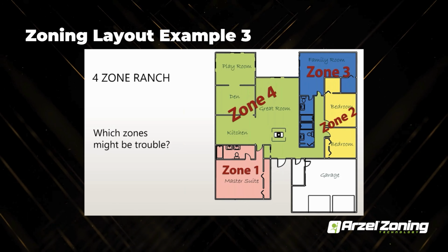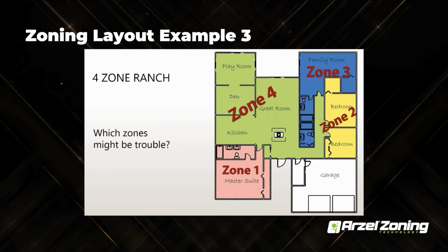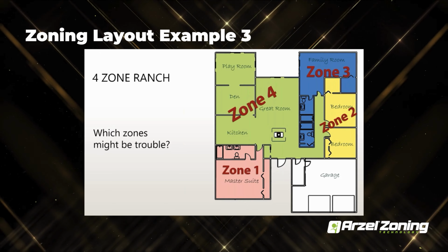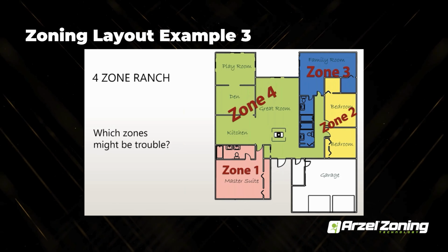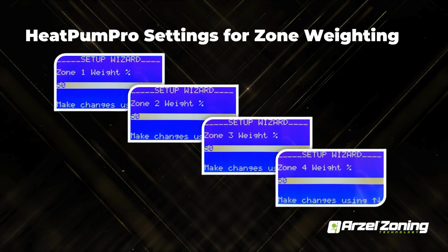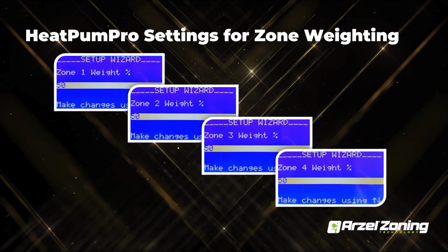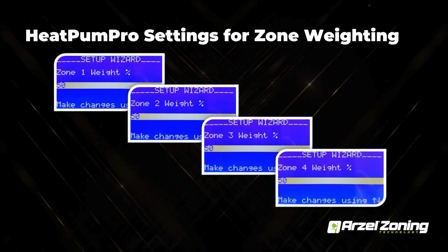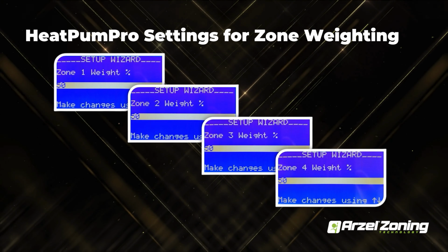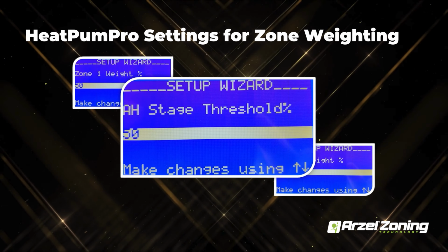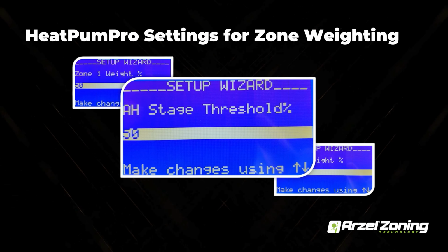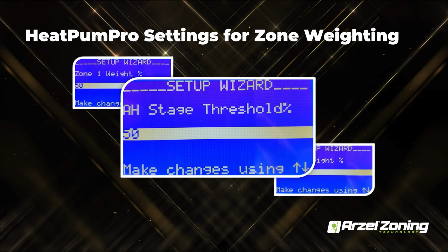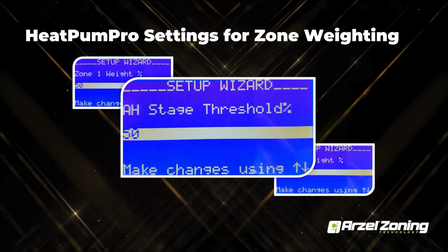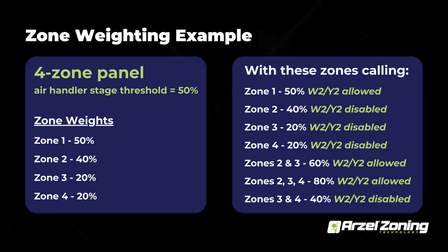If you do that, you can definitely zone a home very similar to this and still achieve the outcome that you're looking for without pushing your equipment past the limits. So with the HeatPumPro, the settings that you're going to be looking at for zone weighting is each zone will have a weight percentage, and then you're going to have an air handler stage threshold. These are the settings that actually play off each other on the HeatPumPro to lock out the second stage operation on equipment. So a couple of examples.